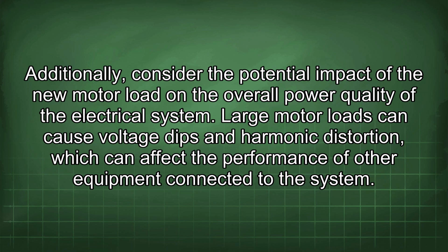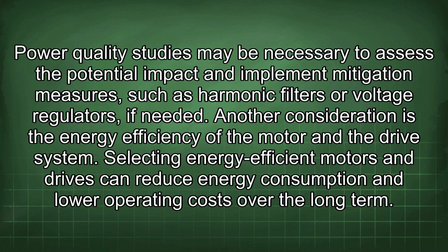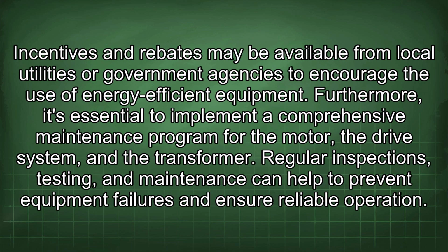electrical system. Large motor loads can cause voltage dips and harmonic distortion, which can affect the performance of other equipment connected to the system. Power quality studies may be necessary to assess the potential impact and implement mitigation measures such as harmonic filters or voltage regulators, if needed. Another consideration is the energy efficiency of the motor and the drive system. Selecting energy-efficient motors and drives can reduce energy consumption and lower operating costs over the long term. Incentives and rebates may be available from local utilities or government agencies to encourage the use of energy-efficient equipment.